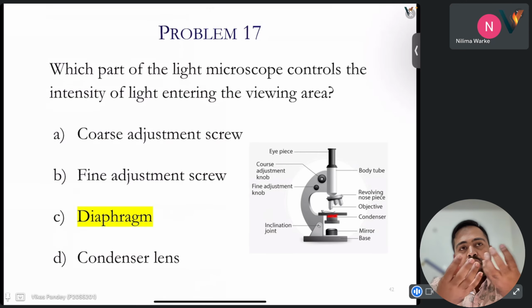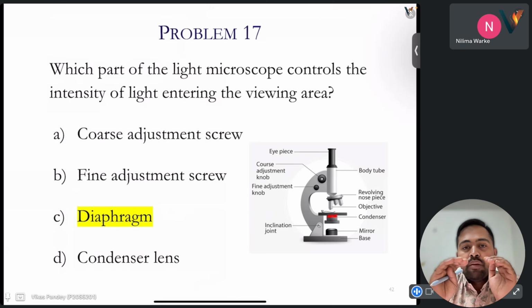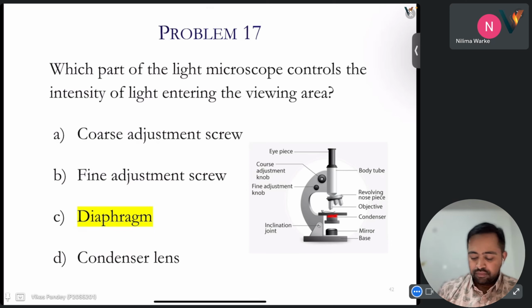how this will concentrate, and then we change the diaphragm, and we will be able to lighten or darken the image that we are seeing. There is in the microscope a small adjustment near the condenser. You will see that from where we can change the intensity, like it will not be circular, a bit like a knob that we can move forward and backward, so that will increase or decrease the intensity.